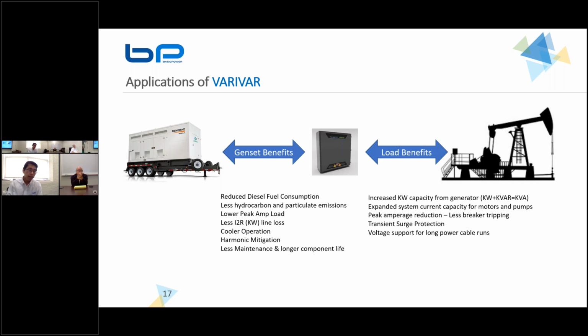Yeah, and another way to emphasize the benefit of just having good power quality is that you don't have to maintain it as much. It turns out that when we spoke with United Rentals, one of the main leading renters of generators, their experts are saying that they're constantly having to replace parts in their generators because of poor power quality, right? When it comes to harmonic distortion, they have to replace the engine heads, they have to replace certain parts because of heating issues and how it'll start vibrating violently due to harmonic distortion. So we can reduce the maintenance and improve the life expectancy of this equipment by just improving the power factor and the harmonic distortion.